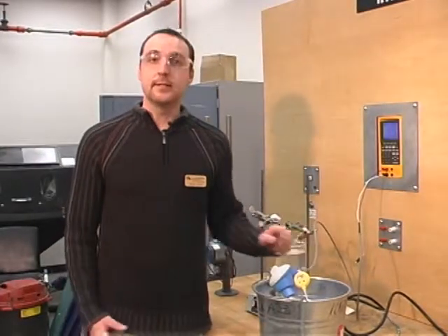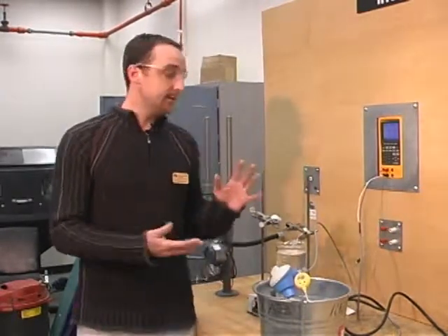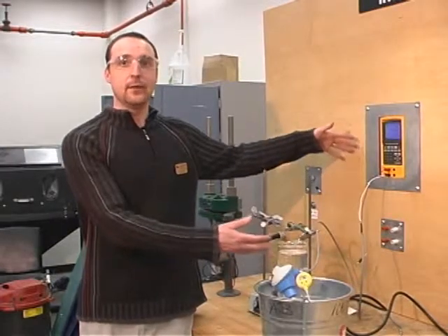Now, for this part of the experiment, if you can just take the resistance that we measured across the two leads, which was the white and the silver wire, and subtract it off each 10 degree increment, because there is that wire resistance that is created with that RTD.